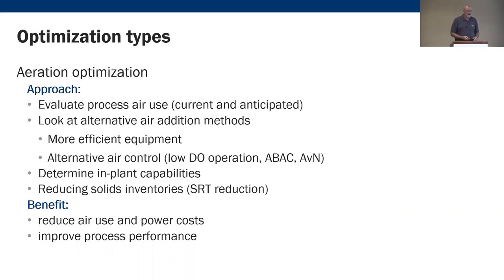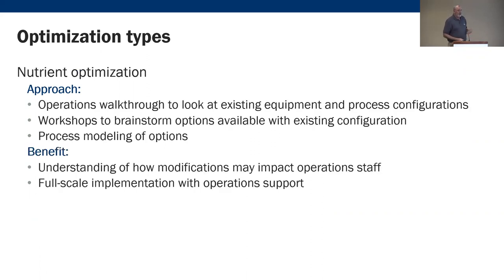Nitrification rates are actually quite good at low DO. This relates to our SRT — the inventory of biomass we're carrying in aeration. The more biomass we have online that's not doing anything, the more money we're throwing out the window — that's called endogenous demand. We also want to walk through the plant with operators and use process models collaboratively to verify what we predict.